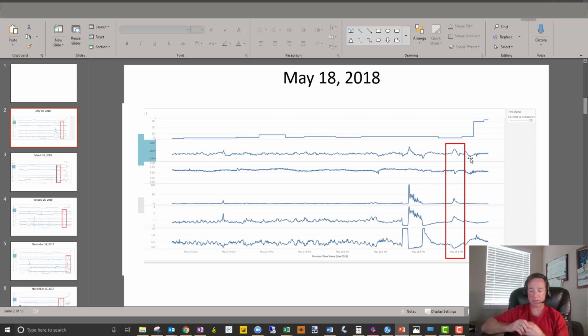So on this, we really had to do some data conditioning on some of these signals, because sometimes this temperature, this second signal here, might go from 1250 to 1280. The next time it may go from 1280 to 1550. The next time it would go from 1280 to say 1330. It would never change by the exact same amount. It would change to varying degrees. The second signal would have to have a certain drop. You see that kind of V-shaped pattern? That's what we needed to really look for.